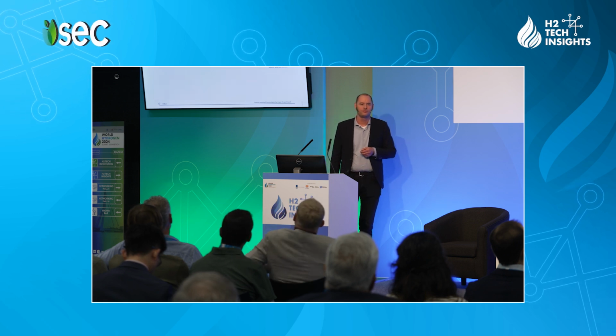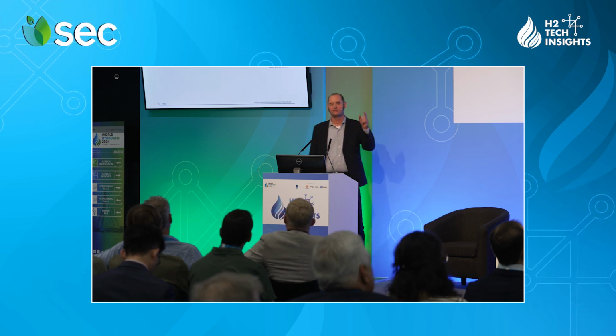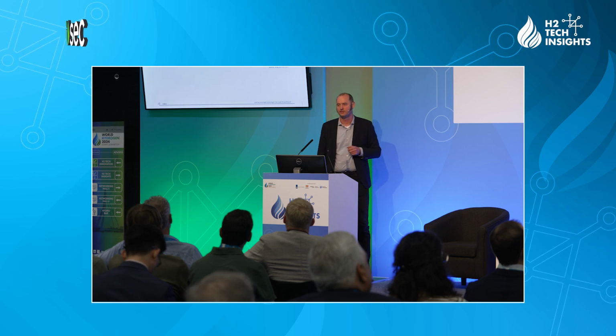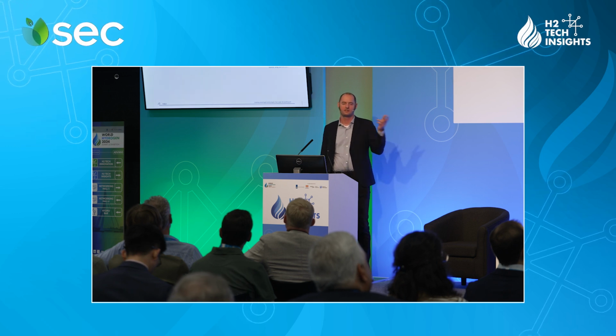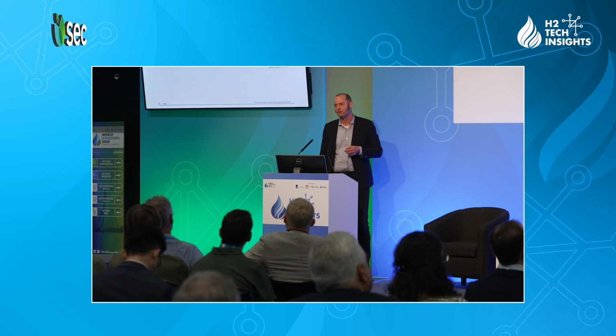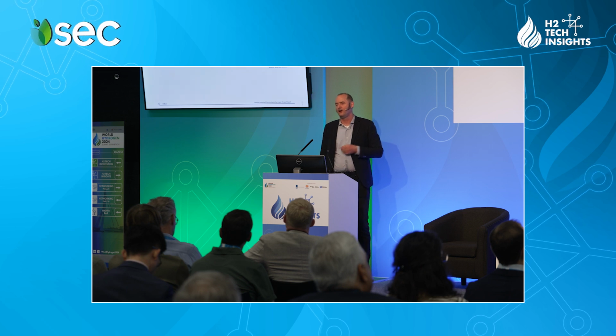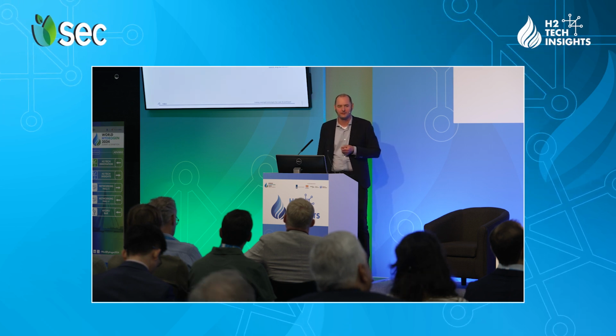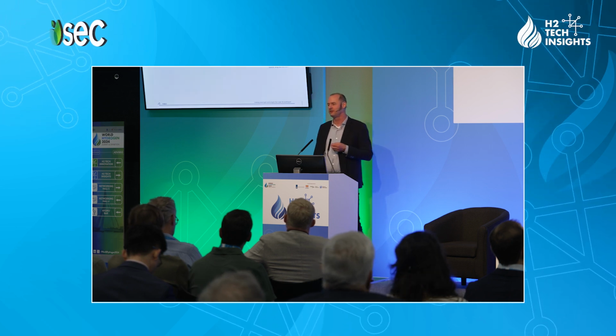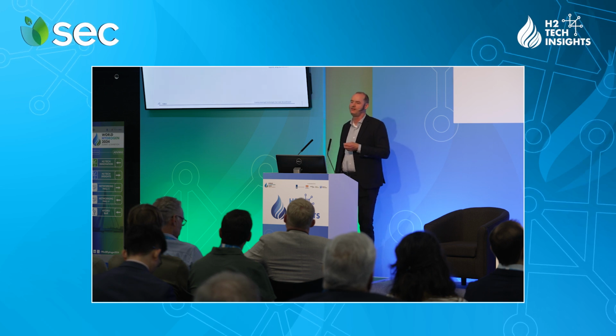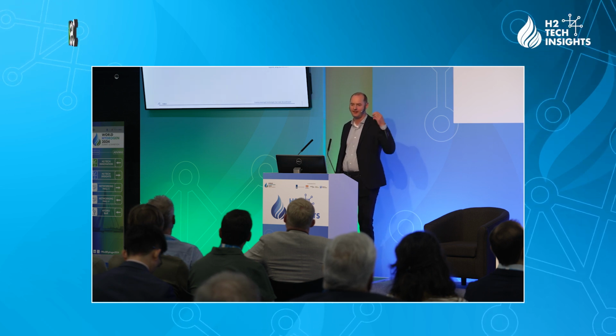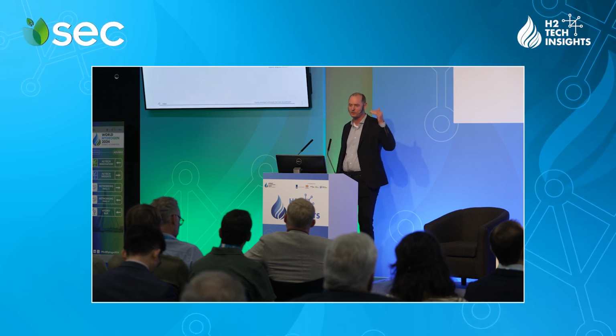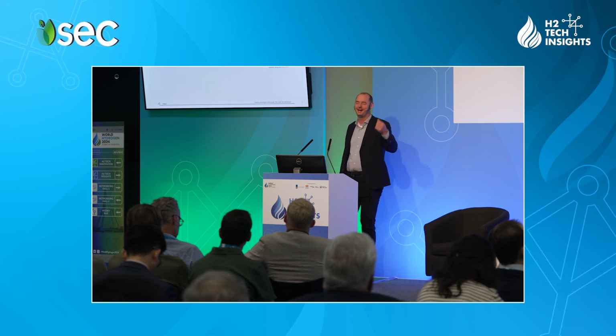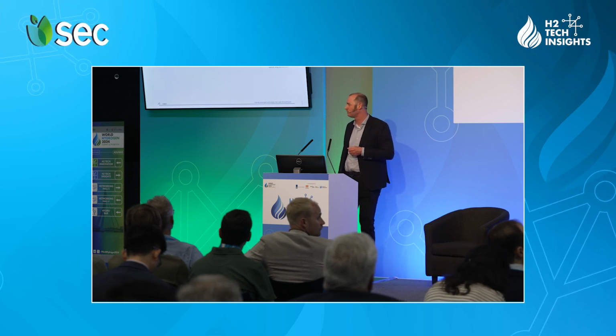One thing that's also often forgotten is the fact that a lot of stacks are still at a relatively low voltage. So you see stacks at 400 volts, 600 volts, 800 volts. From an electronics perspective, the efficiency of the conversion is simply the highest at the higher voltage. And it's limited by the low voltage directive. So ideally, you would have a stack at 1500 volts. And eventually, we'll get there.